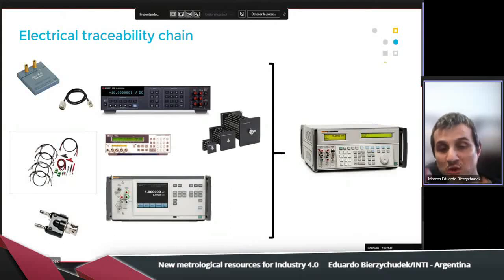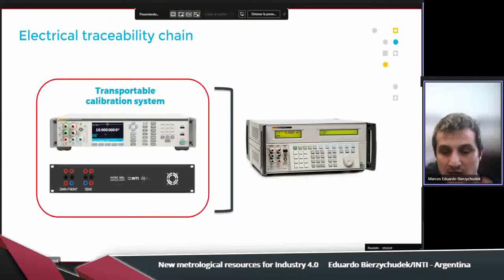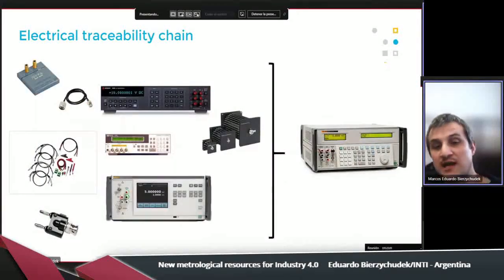So why do we try to modify this system? First, because this, as you can see here, is semi-automatic. You have to be changing between different instruments. And second, specifically the AC voltmeter is a very expensive instrument, with a very expensive calibration, and it's quite difficult to think that a private company in Argentina would buy one of these instruments to calibrate the multifunction calibrator, because it's extremely expensive. So for that reason, we are trying to make this automatic, simplified system that can be useful to perform the calibration and can be of interest to private companies in order to give the service, with a reduced range, of course.